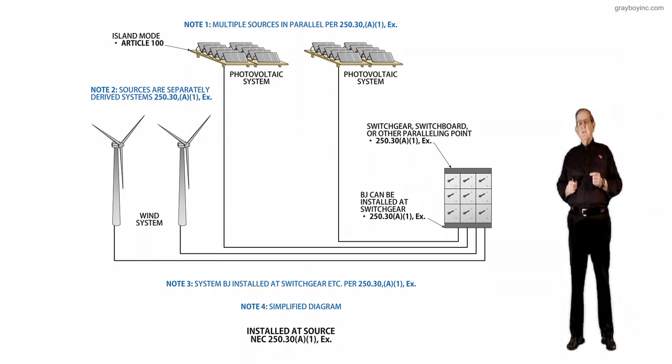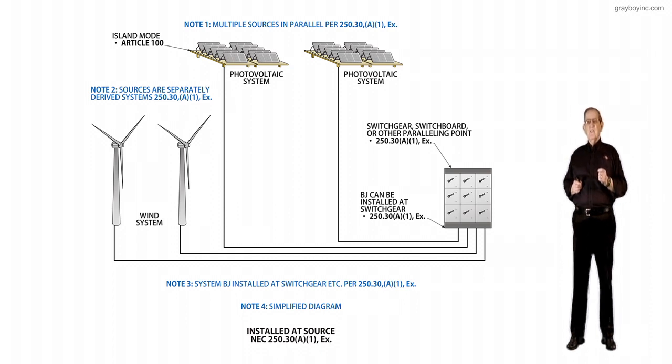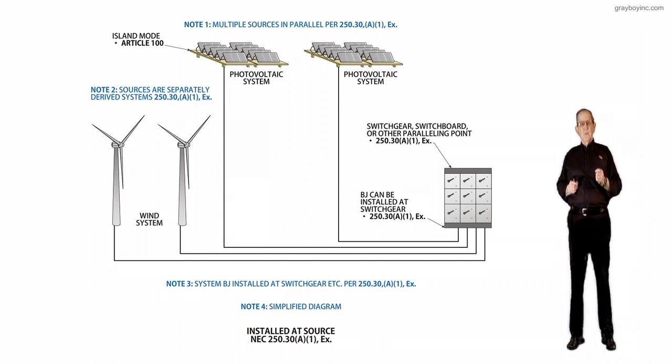The exception would allow the multiple sources to be considered as one separately derived system, and that's important, one separately derived system, and that the system grounding could be made at a single point in the switchgear, switchboard, or other equipment where the paralleling of the source is accomplished.